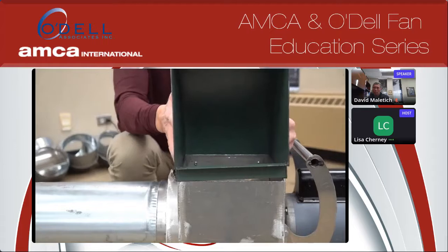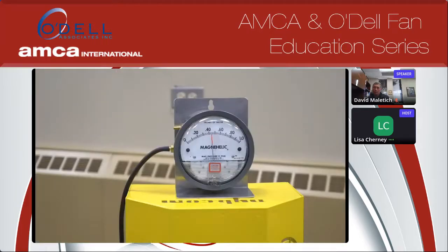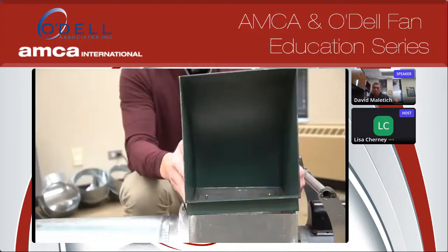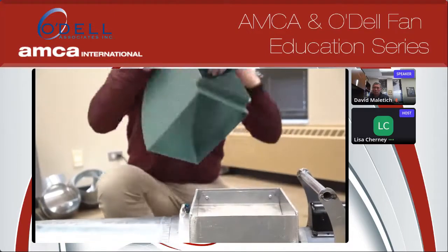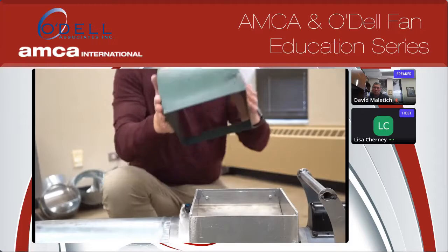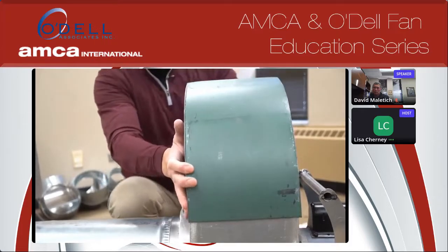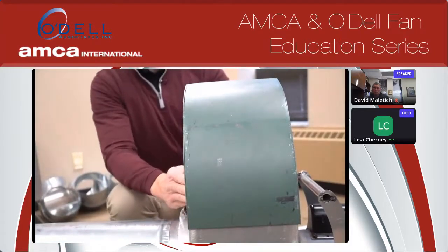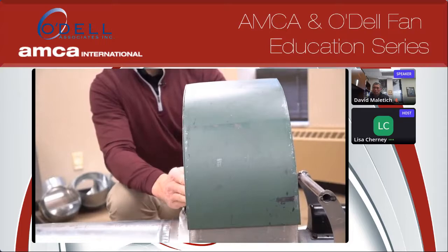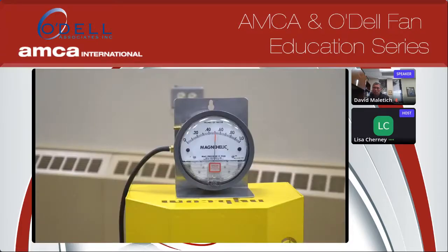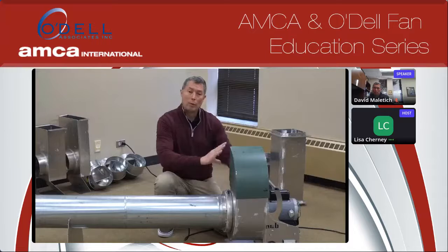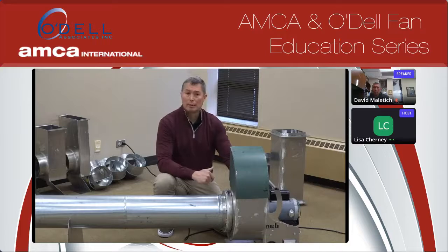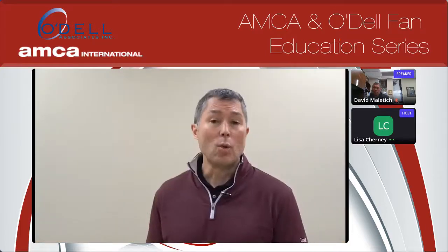So if I put the elbow on this way, notice the performance is decreased when you look at the Magnehelic gauge. Now if I take that same 90-degree elbow, turn it 180 degrees, and now the outside follows the volute shape, you notice that there's very little change in performance when we look at the Magnehelic gauge. Then we can put our straight run of ductwork here. It'll allow the velocity profile to even out, and we can get our static pressure regained with very little loss.